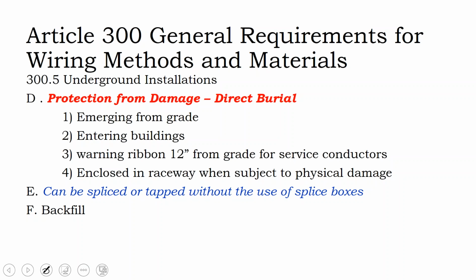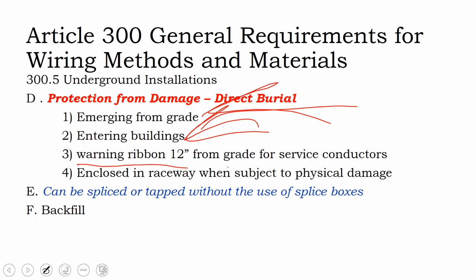And so if you're doing a trench, you may just throw your direct burial wire directly into the trench. And so the question is, well, if I have direct burial wire going directly into the trench, where does the conduit end and where does it begin? And if you have direct burial cable emerging from grade, it needs to be protected from physical damage. You know, entering into buildings, it needs to be protected from damage. You need to put a warning ribbon above your service conductors so that when you're digging, you dig up the warning ribbon before you get down to the conductors. So anyone operating a trencher or a backhoe, you know, they know what they're doing. Well, that doesn't mean you don't call before you dig, but if you're burying power lines in the ground, you need to give people a warning label. Otherwise, who knows what's going to happen down the road in terms of your liability if you're not following code.